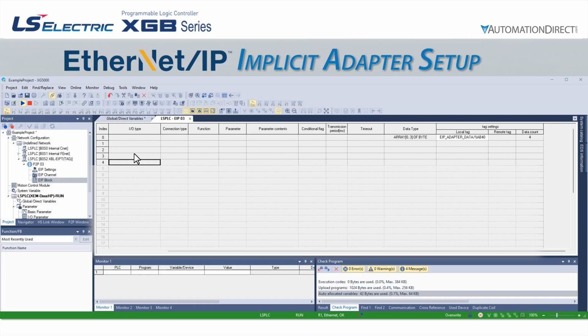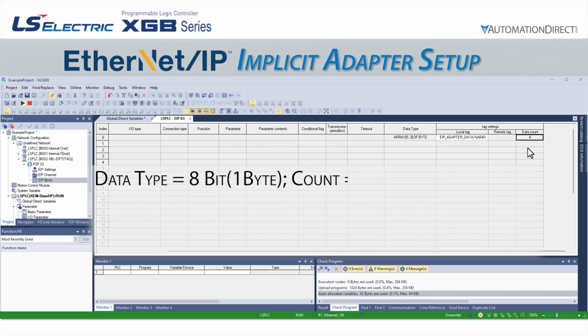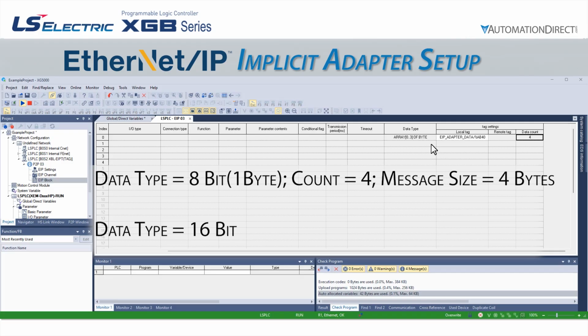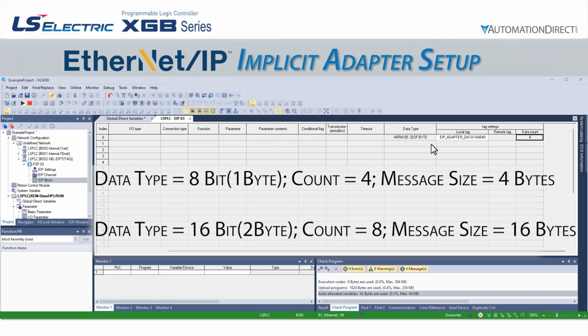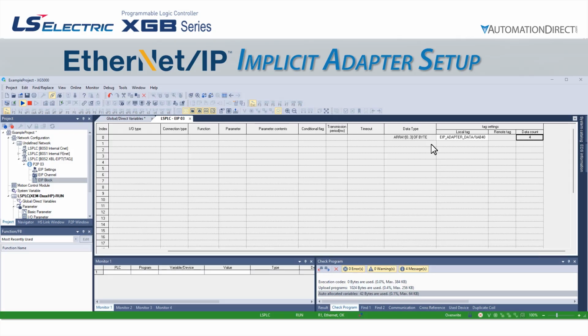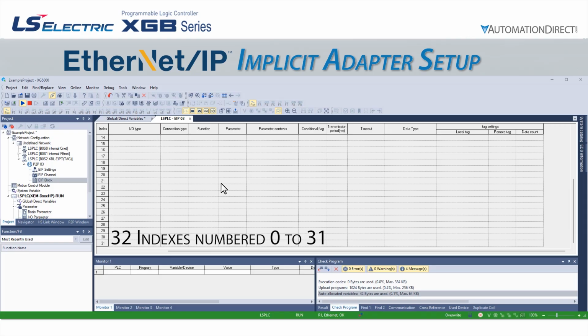The data size for the scanner will correspond to the data type and data count columns. If our data type is 8-bit and the data count is 4, we will have an input and output message size of 4 bytes. If, however, we are using a 16-bit type and a count of 8, for instance, the input and output message sizes will be 16 bytes. In this way, we can access up to 32 different variable arrays for input or output data, with the LSPLC acting as an implicit adapter.